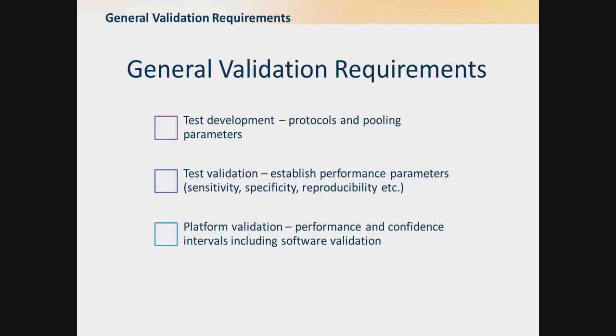The general validation requirements include loads for test development, test validation and platform validation. These are central themes across most regulators and include validation of the protocols, the performance parameters and confidence intervals, including that of software.